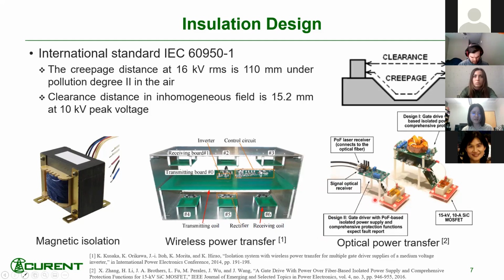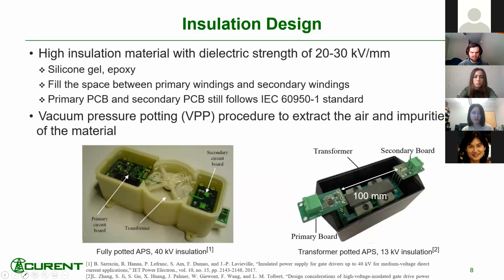This is limited because optical power is limited at the current stage. And what I'm mostly focused on is the insulation design of the transformer. We use high insulation material with extremely high dielectric strength. This dielectric strength is much higher than that in the air, so this would reduce the clearance distance between the windings.